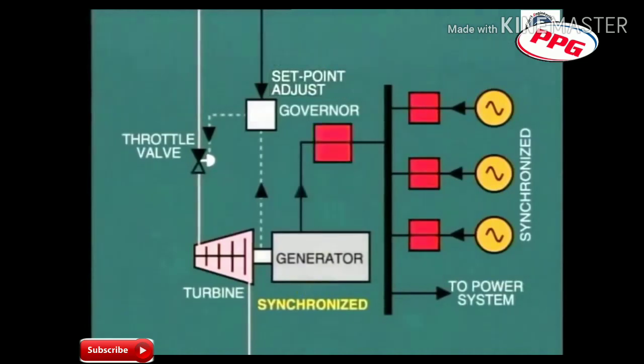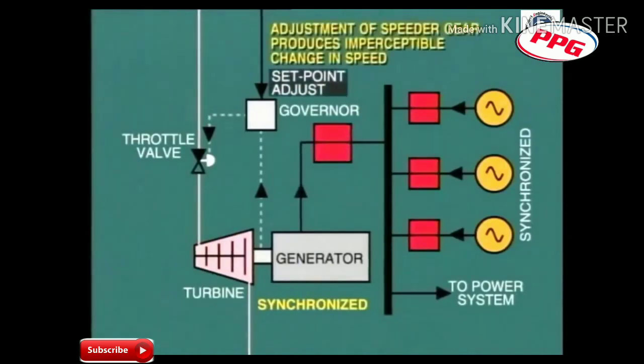However, when the turbine is on load and the generator is synchronized to other machines, any adjustment of the speeder gear produces an imperceptible change in generator speed.